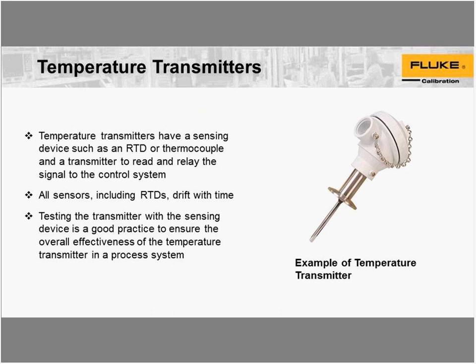So we're going to talk just a little bit about temperature transmitters too, because the plant is set up to provide 4 to 20 milliamp calibration. So just really quickly, a temperature transmitter is a temperature sensor like we've already talked about, a PRT, that is connected to a measuring head that is a 4 to 20 milliamp circuit, and basically converts the resistance of the PRT sensor to a milliamp signal that ranges from 4 to 20 milliamps, and is variable because the temperature range that's being measured is assigned to the 4 to 20 milliamp range. So 20 milliamps is the full scale, 4 milliamps is the zero, the bottom of the scale.